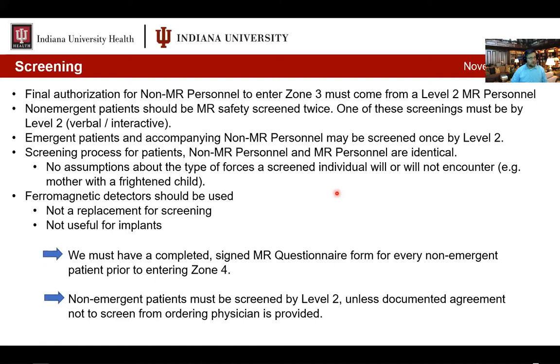You should always use ferromagnetic detectors. Recognize that they are not a replacement for screening, though, and that they are generally not useful for implants. Some subcutaneous implants can be detected, but you should not use ferromagnetic detectors as a means by which you verify that a patient does not have implants, because generally they do not work for implants, especially the wall-based detectors.